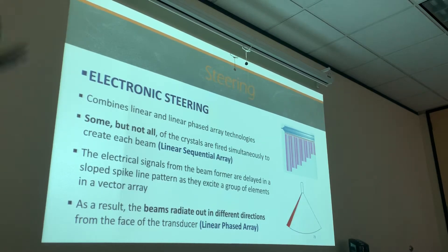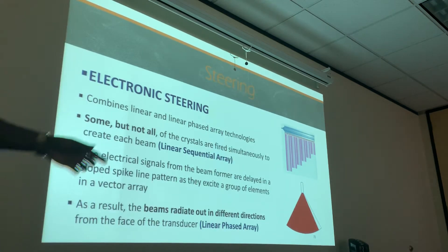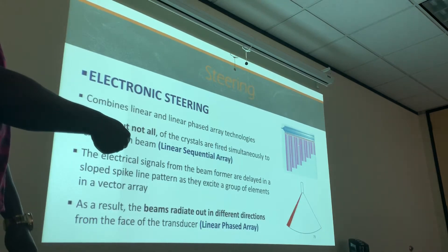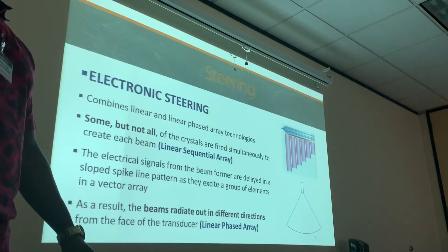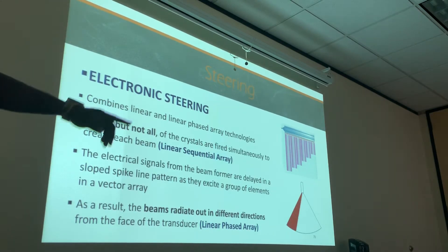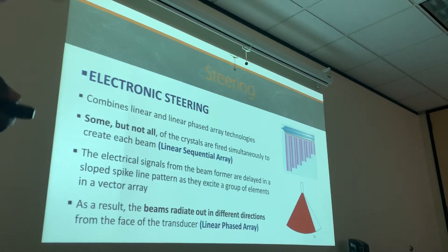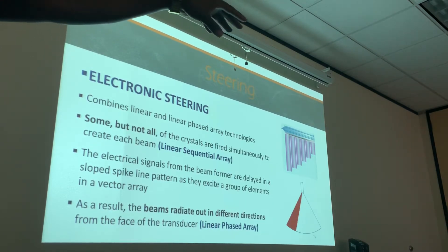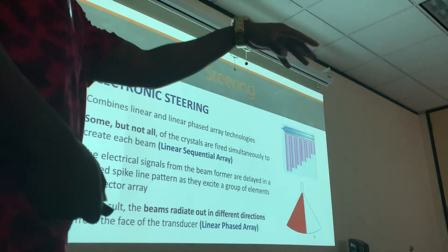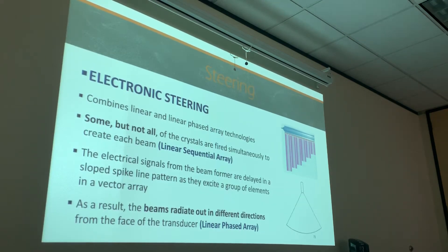It combines linear phase and linear sequential array technologies. When it comes to linear sequential array, some but not all of the transducer elements are fired simultaneously to create the sound beam. With linear phase, all of the elements are being fired basically at the same time to create one beam. The electrical signals from the beam former — which is in the ultrasound system — are sent to the transducer. That's how we get our electronic steering and electronic focusing.